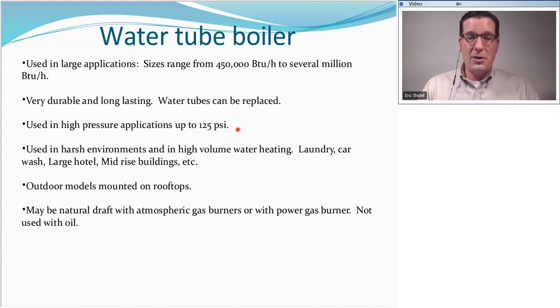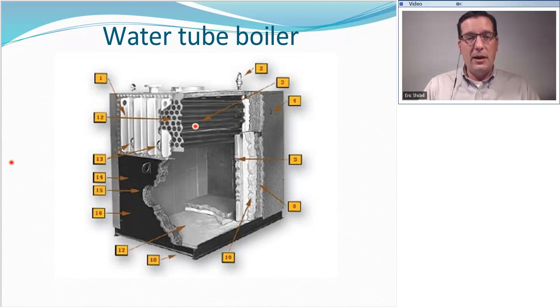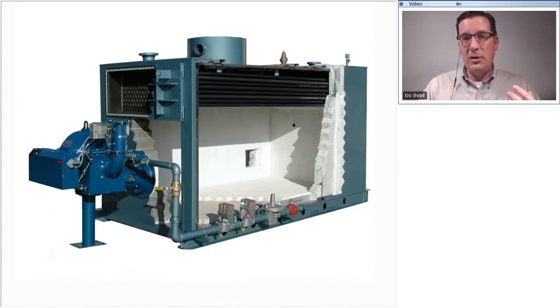Water tube boilers are chosen because often the applications that they're in demands that kind of boiler. So if you're looking for greater efficiencies, you may be out of luck. Water tube boilers are not very energy efficient because you can see most energy efficient designs have very small passageways. Here we have relatively large tubes, right? They're not rifled, they're just smooth, plain steel. We don't have fins on the edges of the tubes to expand the surface area or anything like that. They're not super energy efficient.